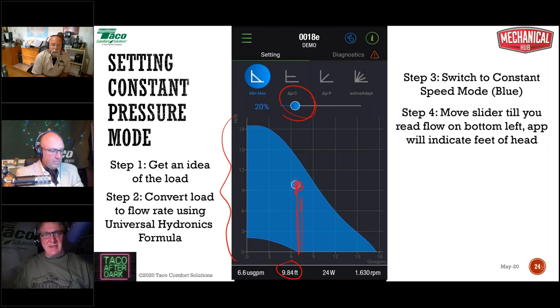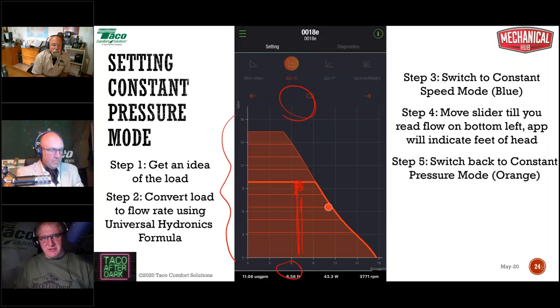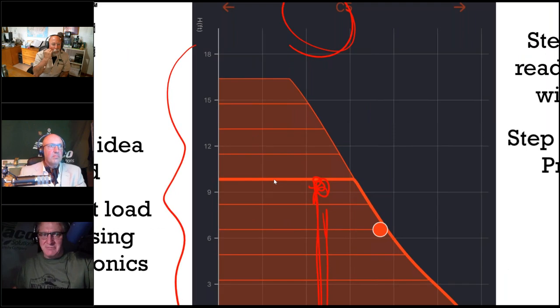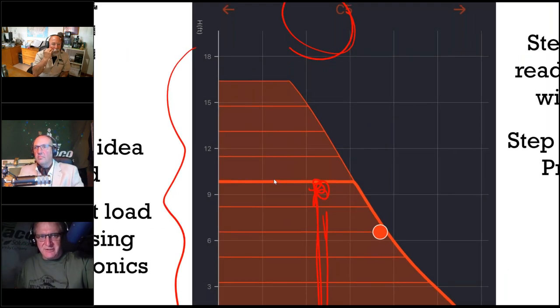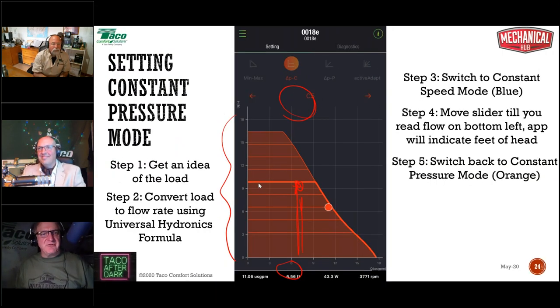It'll indicate the head. Then I go back to constant pressure, and just by touching the screen, you can select different performance curves. What I'm doing, you can't tell, I'm touching it right there. If I touch that screen, I can go to the 10-foot constant pressure line. And if I wanted to go to the one above it, I just touch that and boop, it'll jump up. I could also change it using these arrows, but it's more fun to touch the line you want.